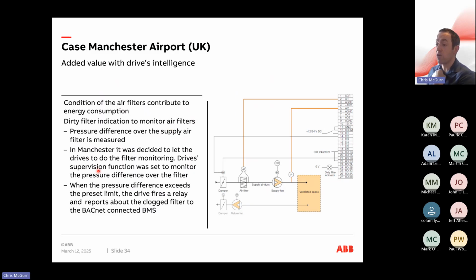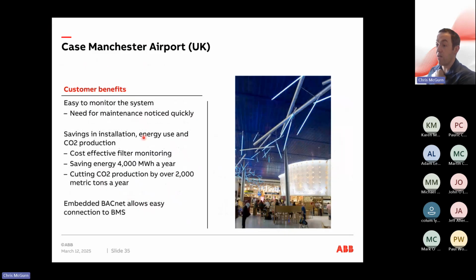So they decided to monitor their systems through the drives. They were set up in a way that whenever the pressure difference exceeded a certain limit, the drives would fire a relay and send reports back to the BMS systems, indicating the maintenance team needed to go out and clean them up. So that was, I suppose, an added value through monitoring of the system itself.